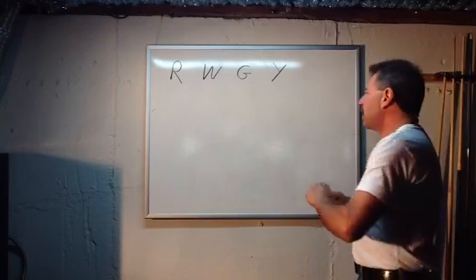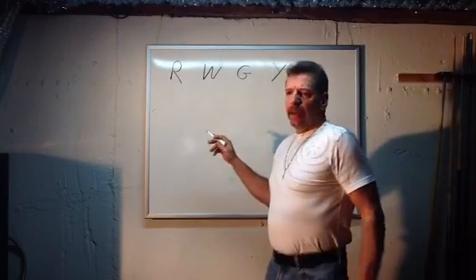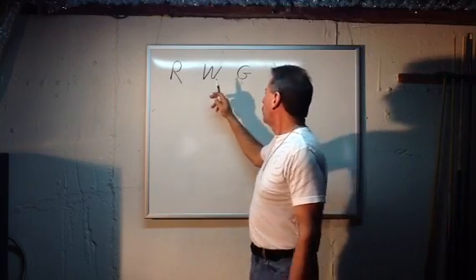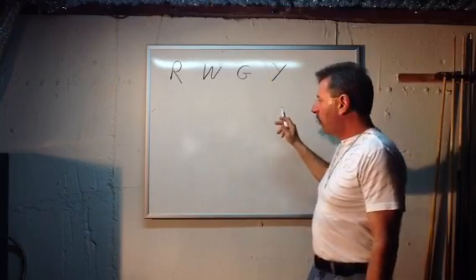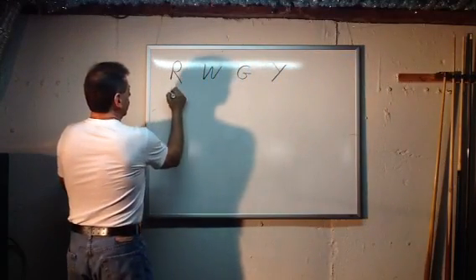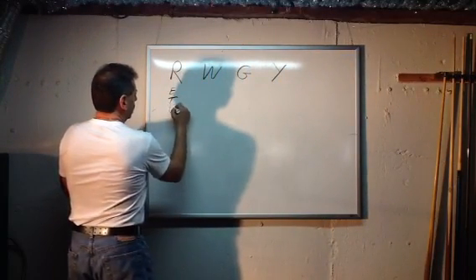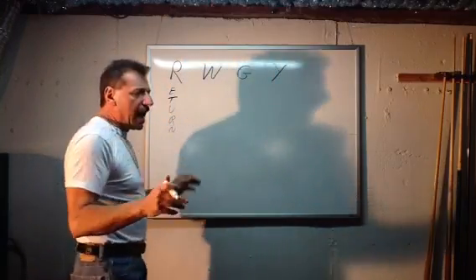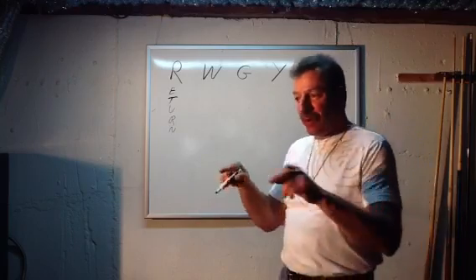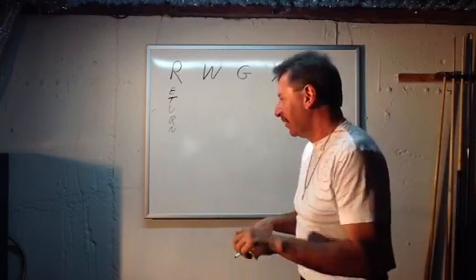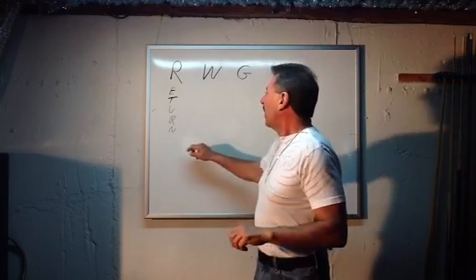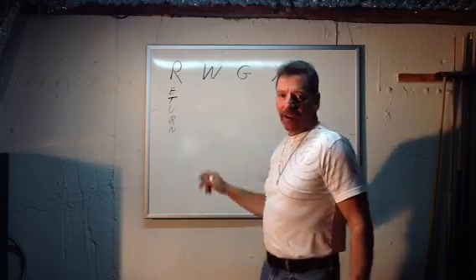The basic thermostat has four letters on the back: R, W, G, and Y. The R is simply the return line, or half of the transformer line. The transformer has two lines coming out of it down by the boiler room, with two screws that give 24 volts out. One of the lines goes to the R, or the hot line, or the return line on the thermostat.